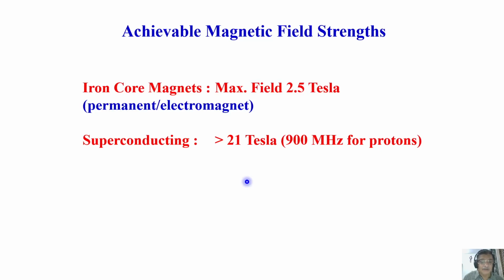will come to the market soon, and will be commercially available. So spectrometer frequency is going up and up. As a consequence, the magnetic field strength also is very high. And to generate such a magnetic field takes an enormous amount of research. We cannot just generate a magnetic field so easily, just because we know the superconducting nature of a certain material, and then make it superconducting, pass current, and generate the magnetic field.